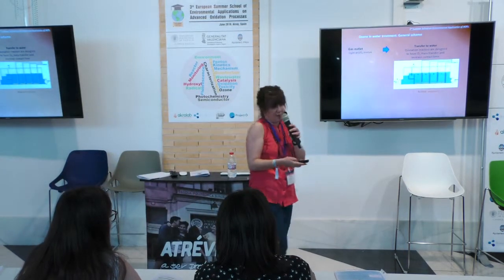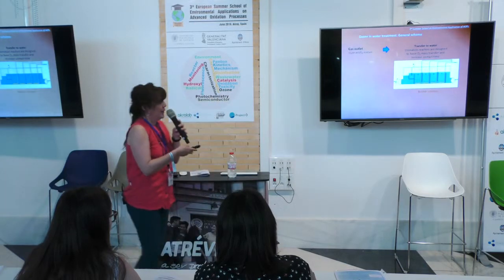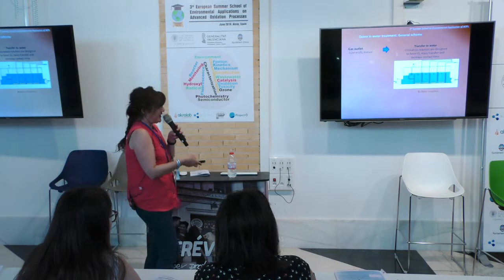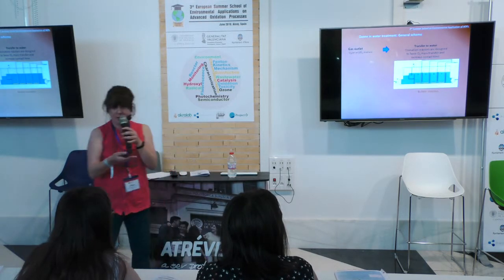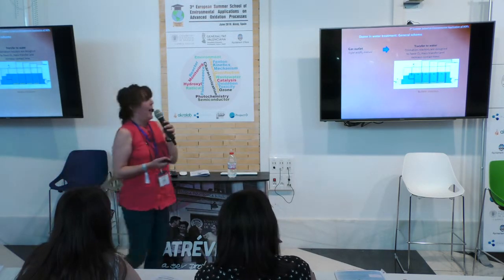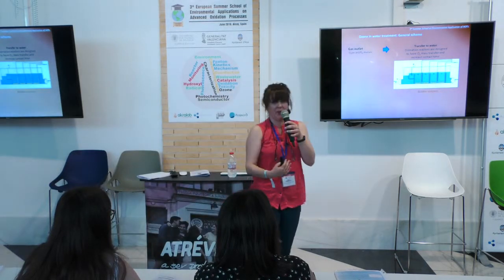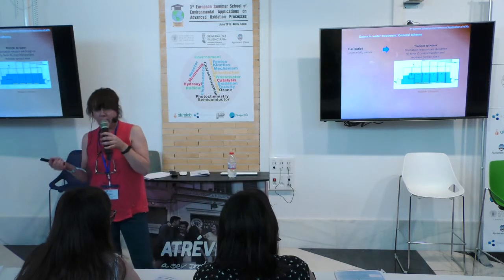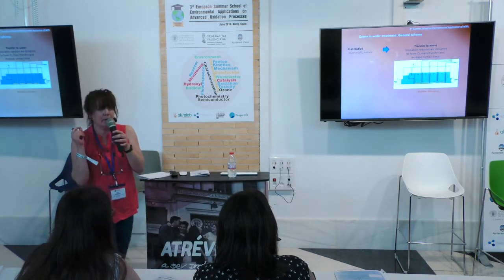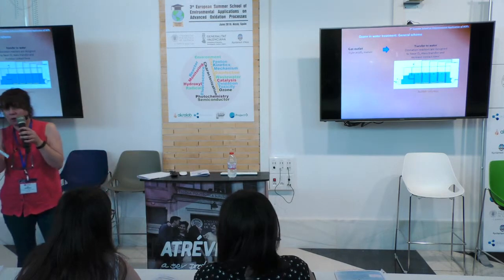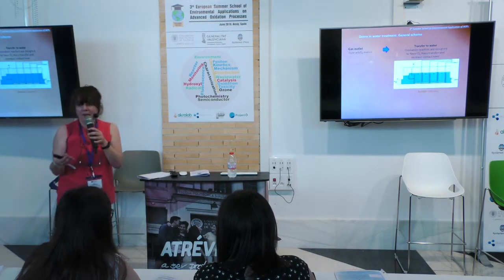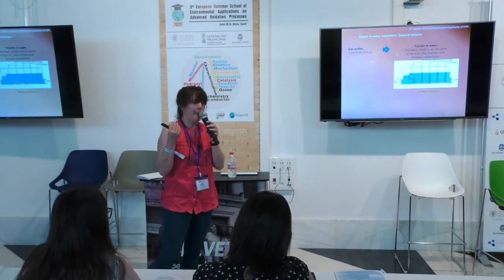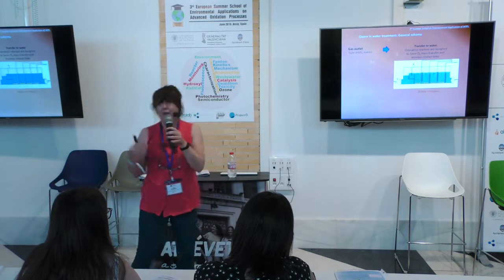So this is one example of an ozonation reactor, where the gas inlet is fed through the bottom, through diffusers, and the water is put in contact with the gas in countercurrent. The finer the ozone bubbles are, the higher the mass transfer coefficient and the higher the retention time.